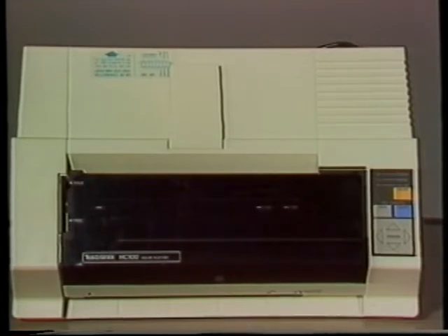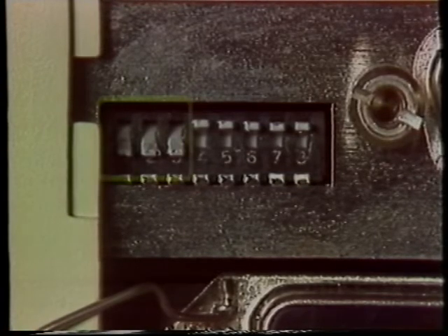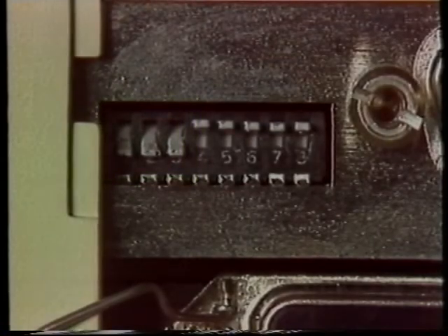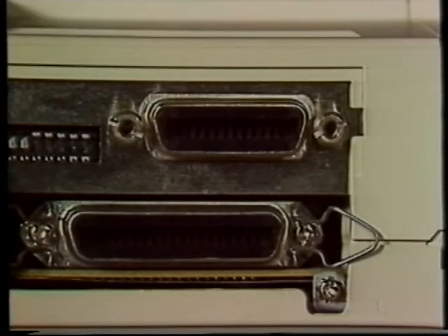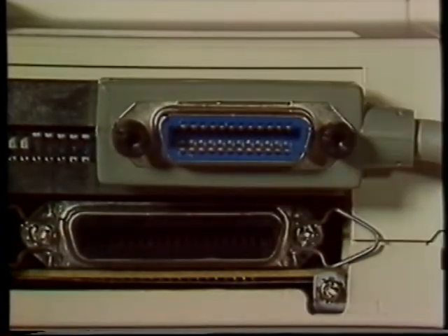The hard copy device is the TEC HC100 plotter using HP graphic language. The HC100 setup for a GPIB interface with the 2400 series digital scopes calls for the first 3 switches to be selected or in the down position. This completes the HC100 setup. Connect the GPIB cable from the plotter to the scope. Now the 2440 must be set up for using the plotter.